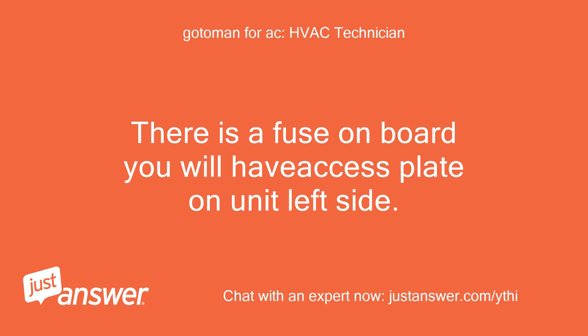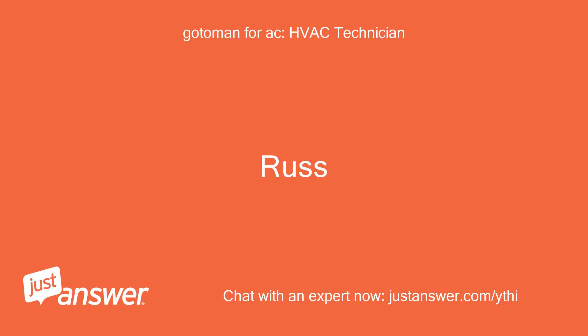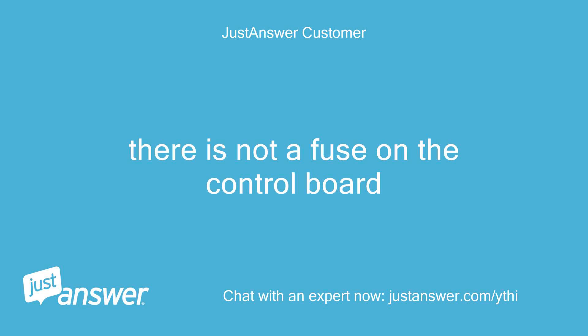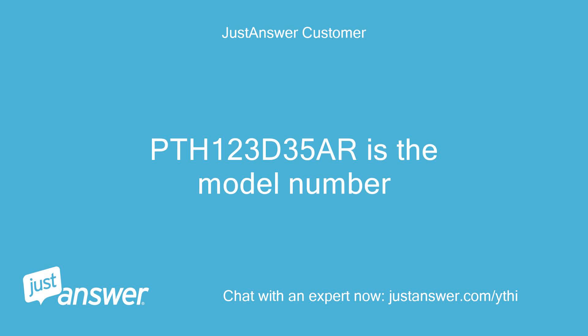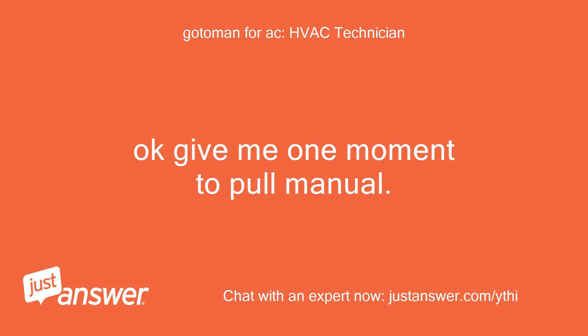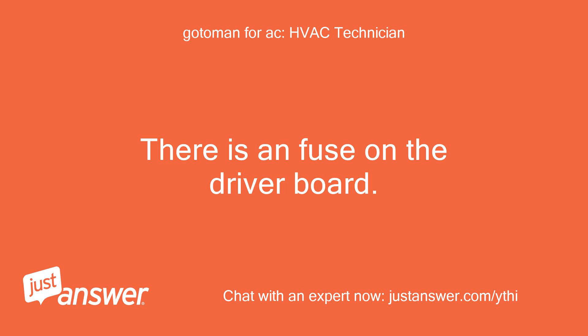There is a fuse on the board — you will have the access plate on the unit left side. Should be a 3 or 5 amp glass fuse. There is not a fuse on the control board; the board is on the right side of the unit. The model number is PTH123D35AR. Okay, give me one moment to pull the manual. There is a fuse on the driver board.